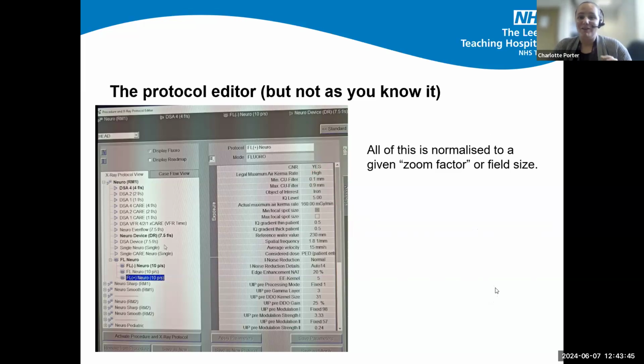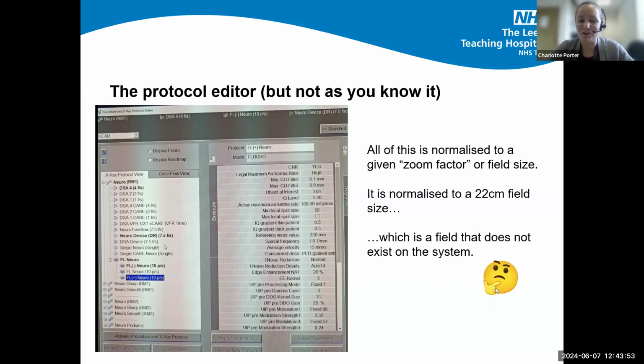The final note is that this is all normalized to a given field size or zoom factor. It's normalized to a 22 centimeter field size, which interestingly isn't a field size that exists on the system. So that's just something to bear in mind if you're wanting to do a bit of maths to figure out what kind of dose rates you should be expecting at different field sizes.